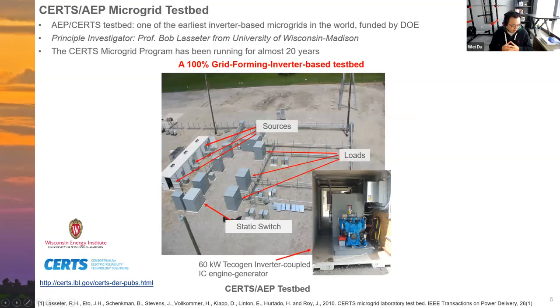After reviewing this basic concept of the grid forming inverter and the droop control, here I'd like to talk a little bit about the CERTS AEP microgrid test bed. This test bed is probably one of the earliest inverter-based microgrids in the world, and it was funded by the U.S. Department of Energy. This platform has been running for almost 20 years, and they have done a lot of pioneering work on grid forming inverters for microgrid operation. I was involved in this program when I was a student. In this section, I will mainly talk about how the CERTS microgrid deals with overload events.